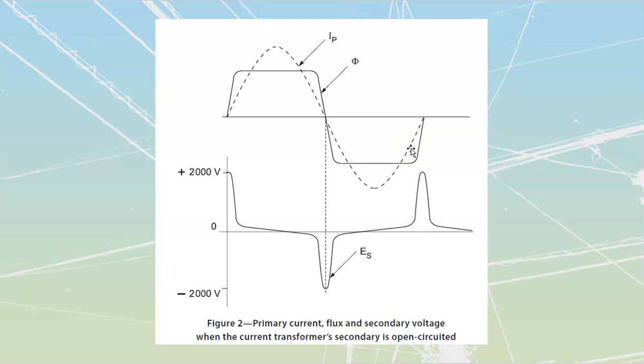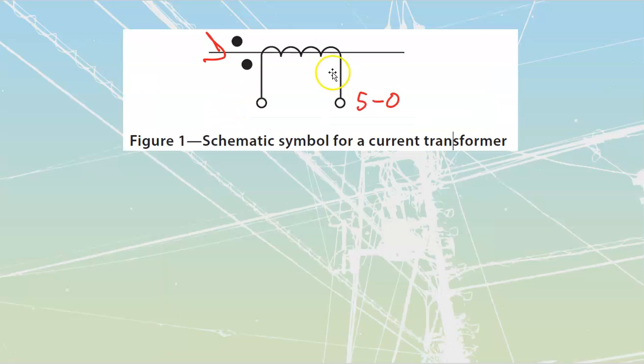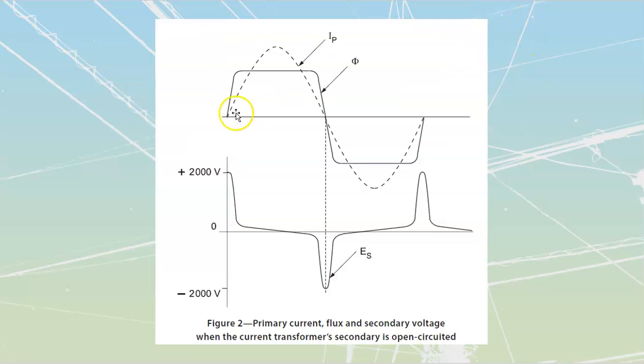So what we get is that as we drive current through this, remember my main load, this is hydro coming in and going out to my main load somewhere inside of that plant. Us opening this does not affect what's happening inside there. Our main load is pulling what's happening over there, so there's still current going through, which means now without that counter EMF, we're going to drive our flux, our Webers, hard into saturation.